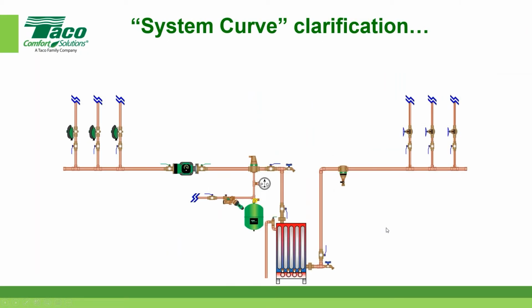So let's clarify what the system curve is all about. Probably the full name for it, let's see if I can remember how to call it, because everybody shortens it up. It is the resistance of the system that you put the circulator into. In particular, this is showing a boiler, a circulator, and 3 zones with corresponding returns from those 3 zones. And the pipe, the valves, the fittings, the links, the heat emitters, all that stuff is going to give a unique signature to this circulator.